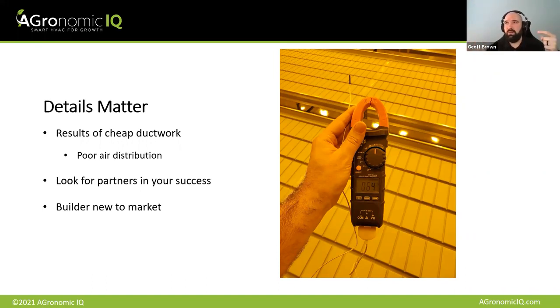and then wonder why no air gets down low. Well, you've all walked into a Costco or a Target and had the fans blow on you. Well, it's literally creating an air curtain. It's designed to block mixing between inside and outside. And if you do that with your air rotation fans, you're going to accomplish exactly the same thing. So intelligently applied air distribution is really, really important.